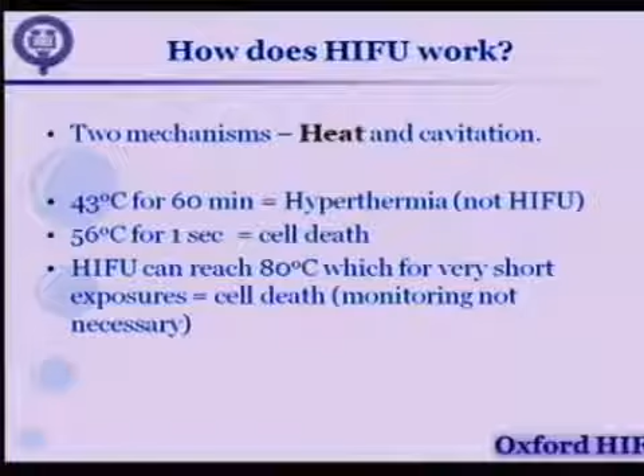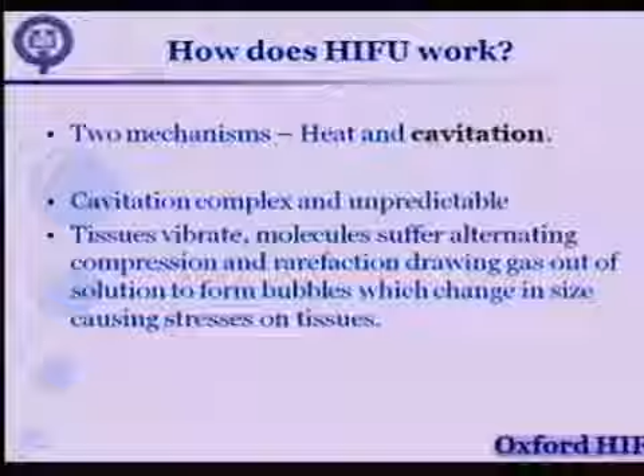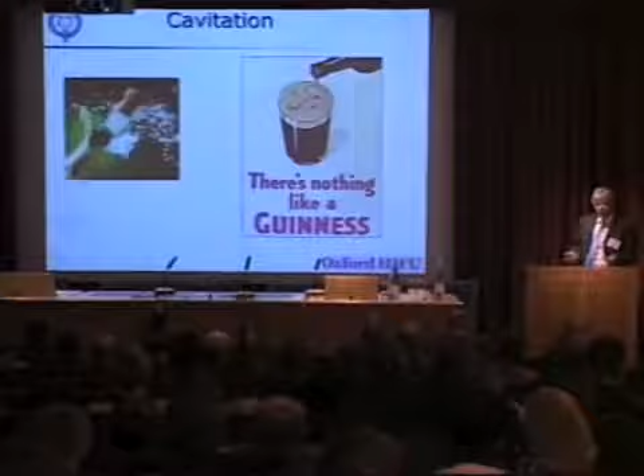Every time you fire this beam, you get a little lesion the size of a grain of rice. And it works through two mechanisms. Firstly, it's the heat, but the second one is cavitation. Cavitation is basically where you get compression and rarefaction, which draws gas out of solution, forming bubbles which change in size. It's a little bit like when you take the top off a champagne bottle, the bubbles come out of solution and cause this cavitational effect. You have stable and unstable cavitation as the ultrasound wave changes: with higher pressure the bubbles are smaller, with lower pressure they're larger, and if they just alternate like that, that's stable.